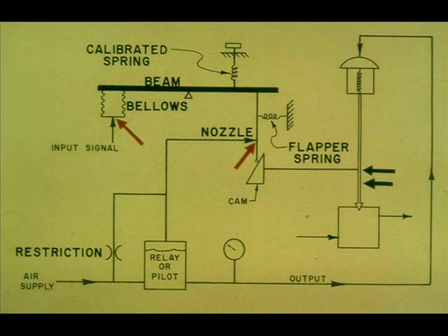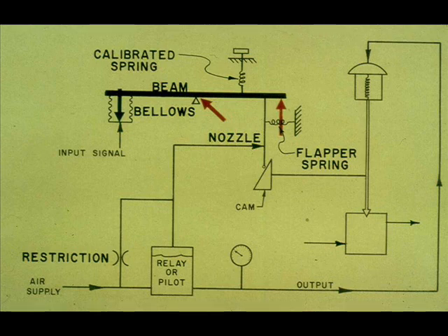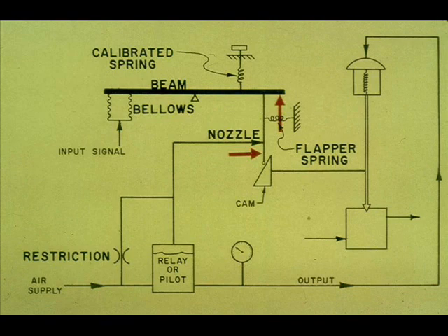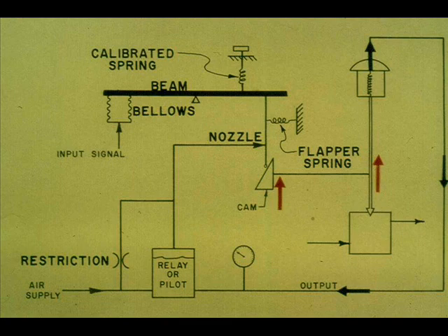The flapper nozzle relationship is restored, but there is a different air pressure in the input bellows and the valve stem has a new position. For a decreasing input signal, the opposite action takes place. The right-hand side of the beam moves upward, the flapper rides up the cam and away from the nozzle, the valve stem moves upward, forcing the flapper back toward the nozzle, and the flapper nozzle relationship is restored.